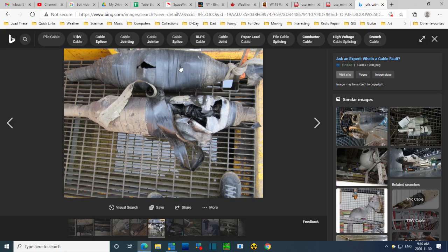They're operating. They get hot and cold every day. The electric power system cycles temperature-wise up and down every day. Everything in it expands during the day, contracts at night. A lot of it doesn't matter, so what if a transformer tank is expanding and contracting a bit? Well, I guess it'll wear out the seals in it eventually. And these cables, because they run, like in my case, or where I used to work, 100 meters to the next manhole, and if you change its temperature 40, 50 degrees C, from peak to minimum, you get a half-inch movement, half-inch expansion of the cable into the manhole.